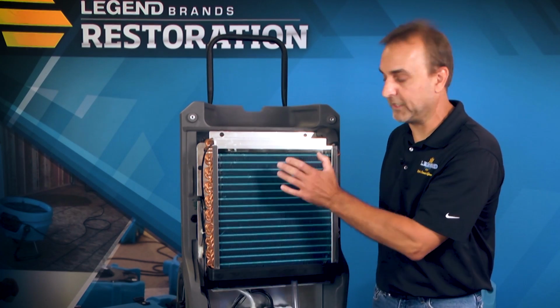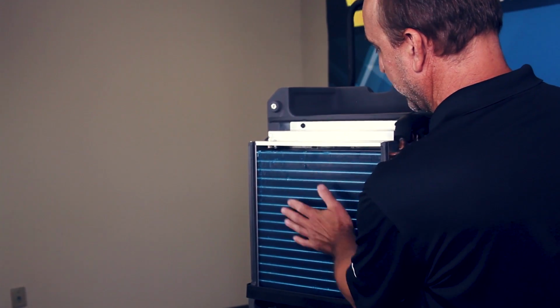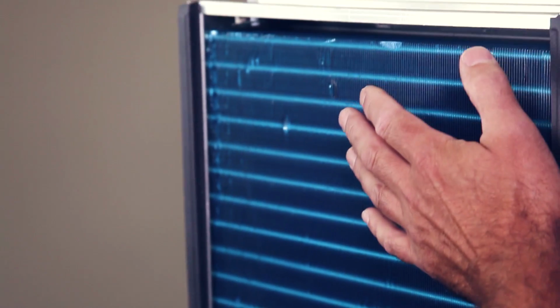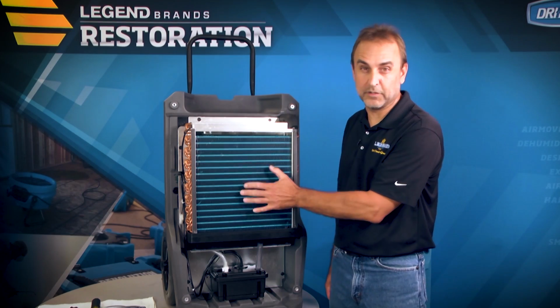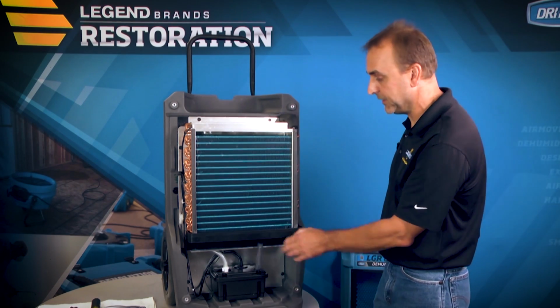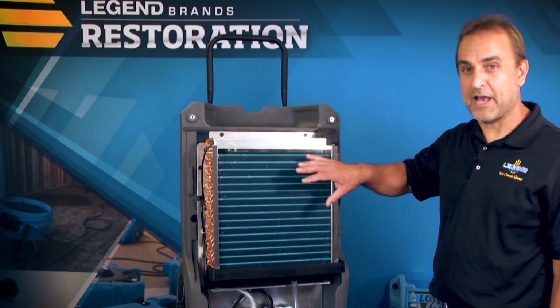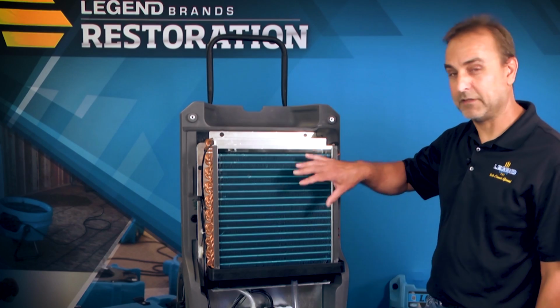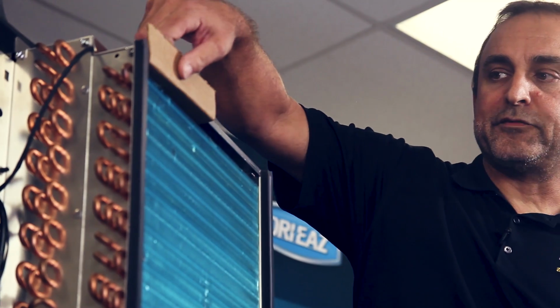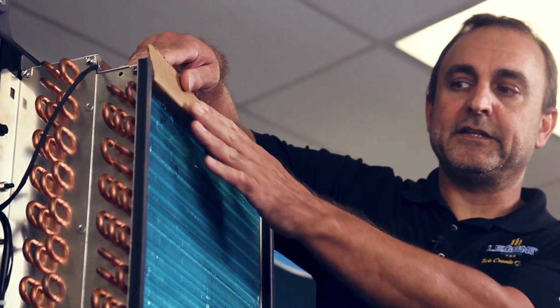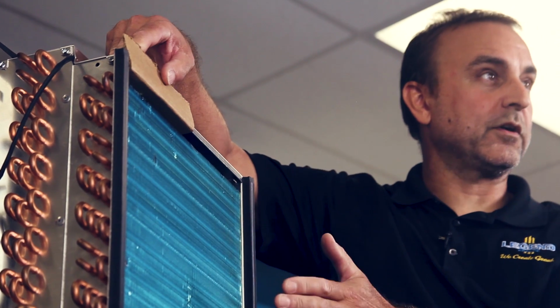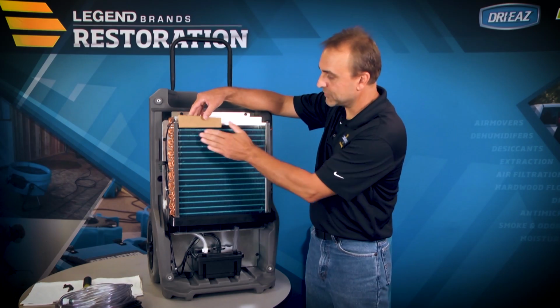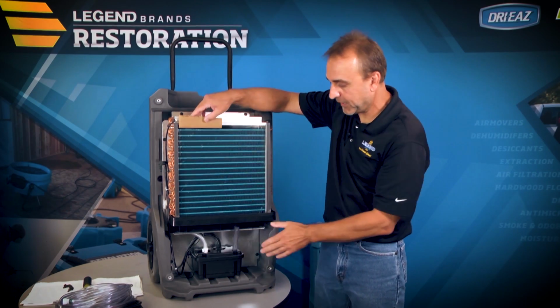Vacuum the coil assembly off. Do not bend the fins, and be careful, the fins are sharp. And be careful, do not put the vacuum attachment up to the coil assembly. You can damage the fins. If the coil assembly does not come clean with the vacuum, you may use an alkaline-based coil cleaner, like all of our other products. After protecting the inlet temperature and humidity sensor from any coil cleaner or rinsing, you'll want to wash the coil assembly down from top to bottom.